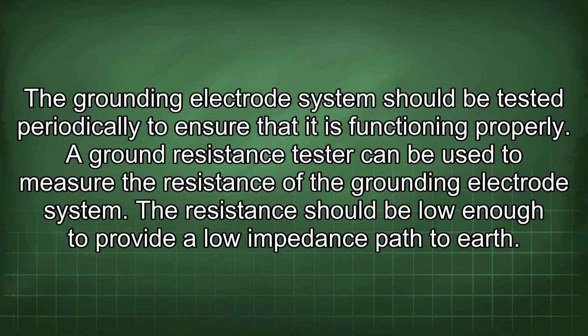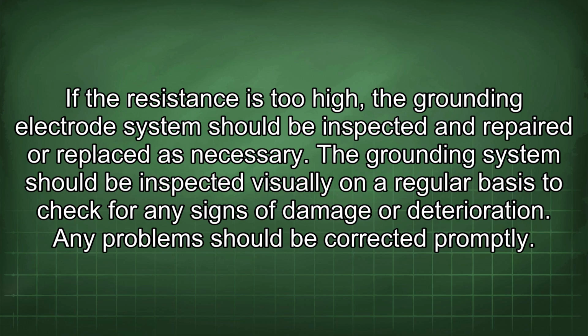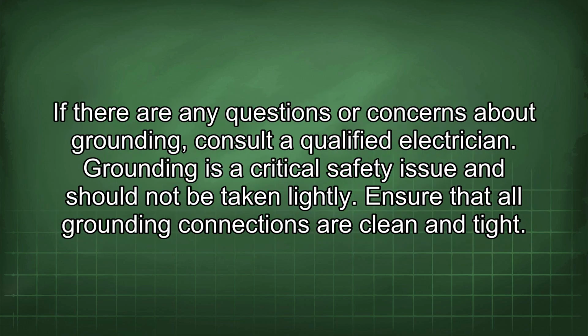A ground resistance tester can be used to measure the resistance of the grounding electrode system. The resistance should be low enough to provide a low impedance path to earth. If the resistance is too high, the grounding electrode system should be inspected and repaired or replaced as necessary. The grounding system should be inspected visually on a regular basis to check for any signs of damage or deterioration. Any problems should be corrected promptly. If there are any questions or concerns about grounding, consult a qualified electrician.